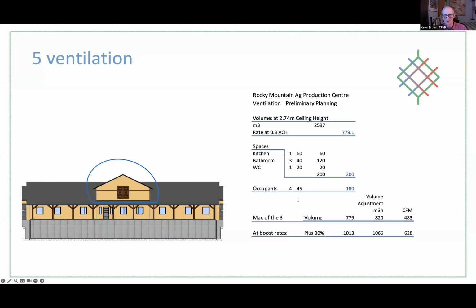So you want the entire space to turn over in fresh air every three hours. And that's the one part of the test. The second part is you take a look at the kitchen, bathroom, and washroom. So in this case, there's one kitchen, three bathrooms in the building, and one water closet, so one WC. And that gives you a certain rate based on boost rates of 60 cubic meters per hour for the kitchen, 40 per bathroom, and 20 for the WC.